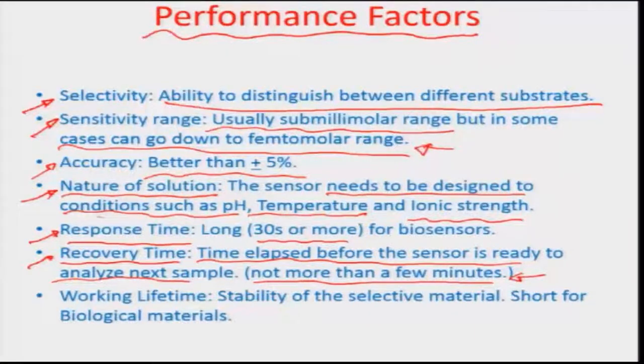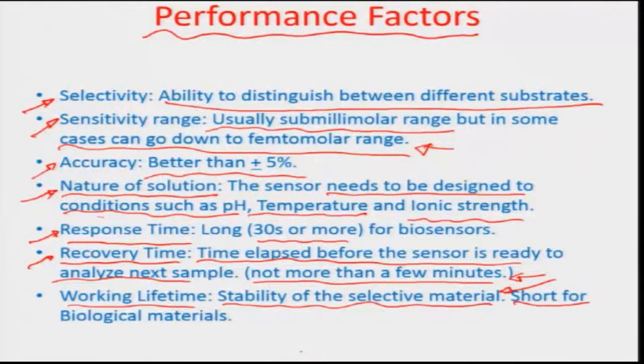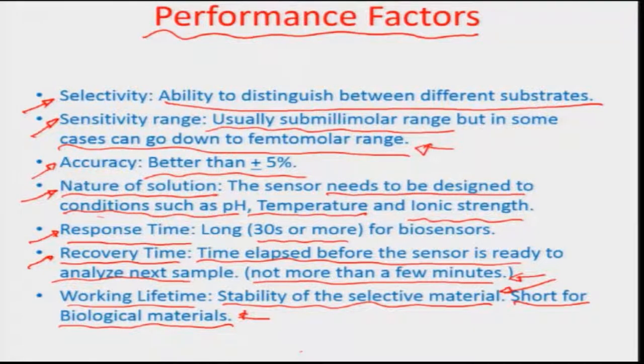We also talk about the working lifetime of a sensor — the stability of the selective material. For biomaterials like enzymes or antibodies used in some sensors, the shelf life may be as low as 2 to 3 months. Before that it is better to use them, and after that one should discard, as the sensor will start giving false signals. The working lifetime forms a very critical function when we talk about performance factors related to sensors.